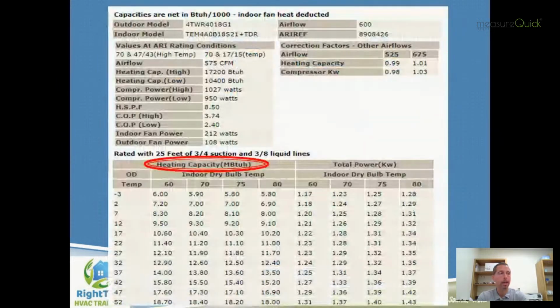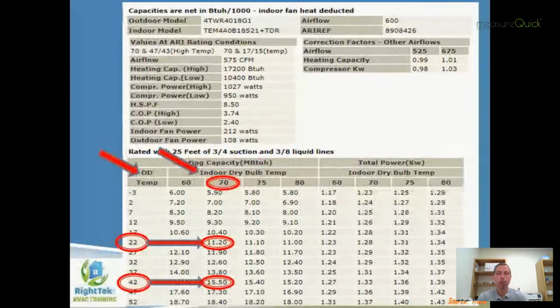So once again, we go into our OEM performance data. I pull up the design performance data for the same exact heat pump that I showed you the data for there on the cooling side. And I want to kind of dig into this a little bit. And what you're going to notice is I can match up, again, my outside temperature, which is kind of down the left-hand margin there, along with my indoor design temperature, which again is 70 degrees per the normative section of Manual J. And I can see what the heating output capacity of that heat pump is as outdoor temperature changes. And you'll notice the trend here as outdoor temperature decreases on an air-to-air heat pump. Of course, the BTU per hour output capacity of the refrigerant side of that heat pump continues to decrease along with that as well.